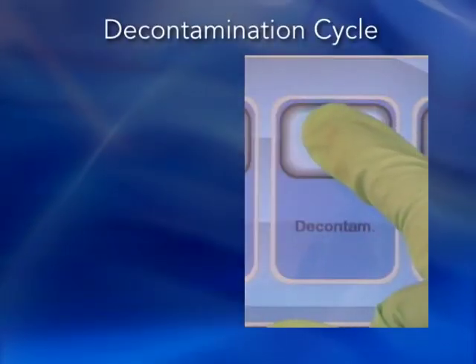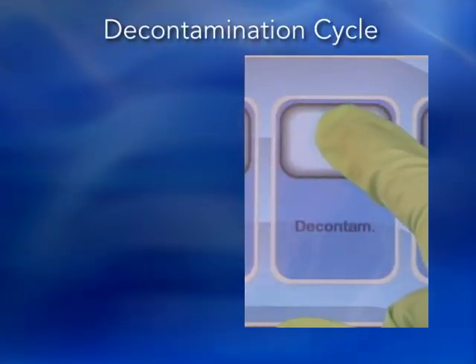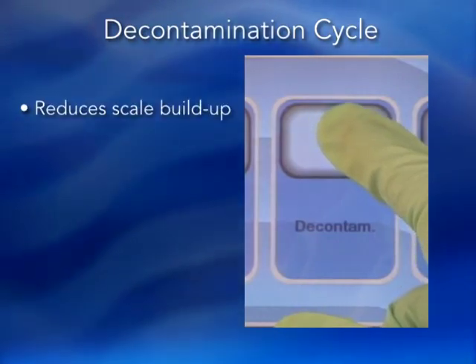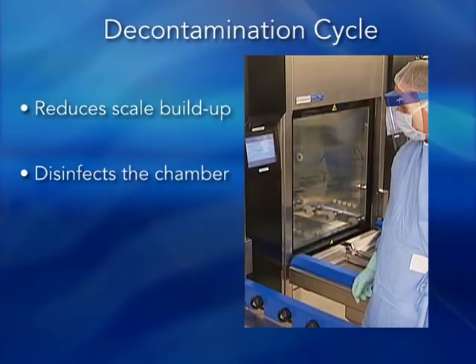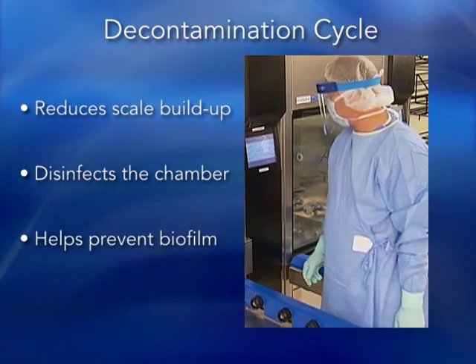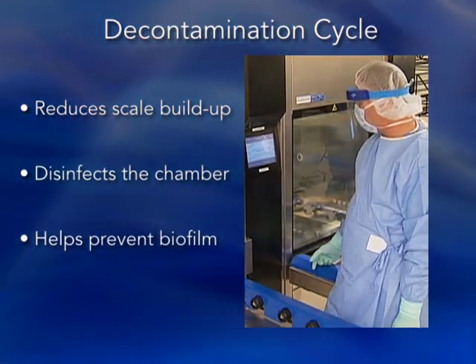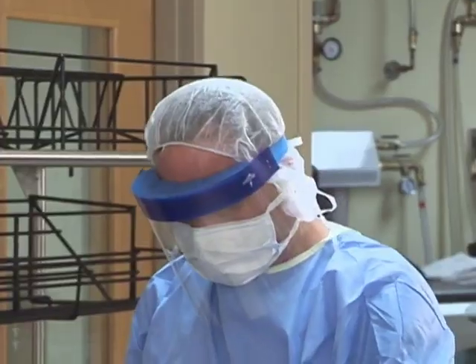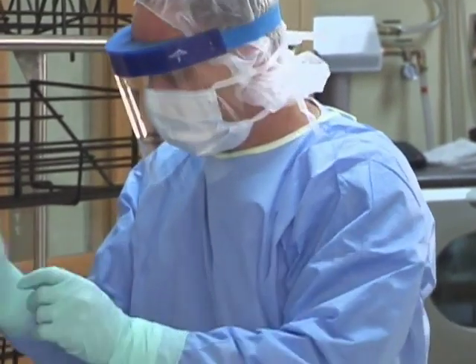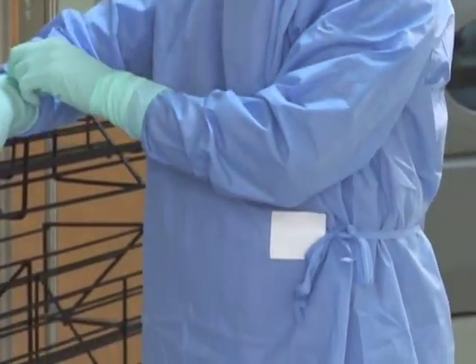Finally, once a week, you'll need to run the decontamination cycle. This helps reduce scale buildup in the chamber and to disinfect the chamber and prevent biofilm from building up inside the chamber, pipes, and filtration system. Before running this cycle, be sure to wear the appropriate personal protective equipment.